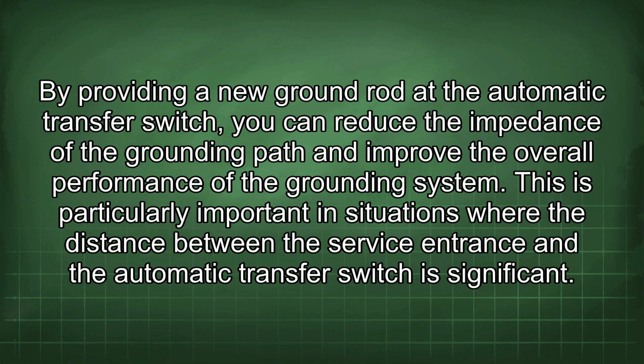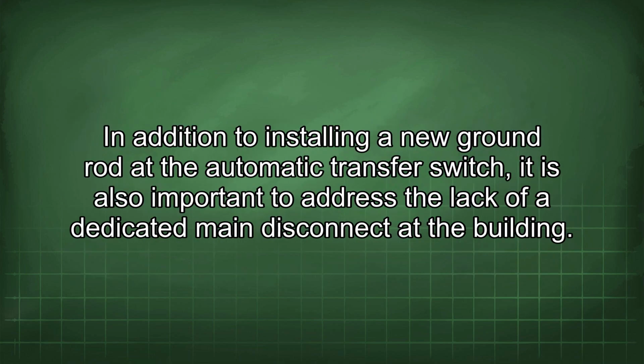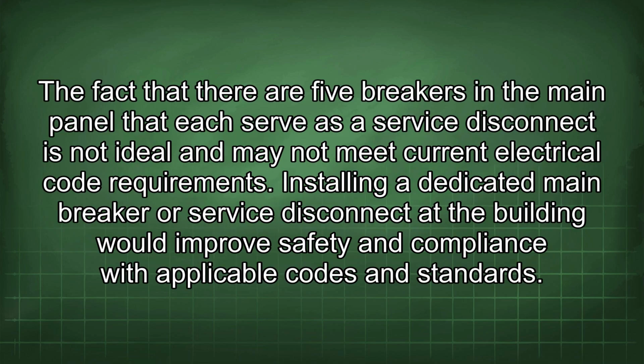This is particularly important in situations where the distance between the service entrance and the automatic transfer switch is significant. In addition to installing a new ground rod at the automatic transfer switch, it is also important to address the lack of a dedicated main disconnect at the building. The fact that there are 5 breakers in the main panel that each serve as a service disconnect is not ideal and may not meet current electrical code requirements.